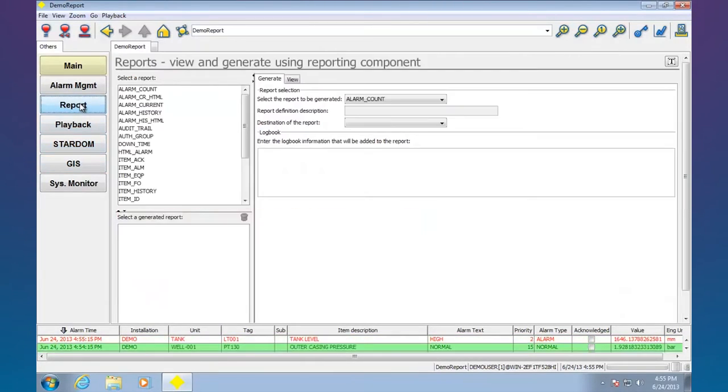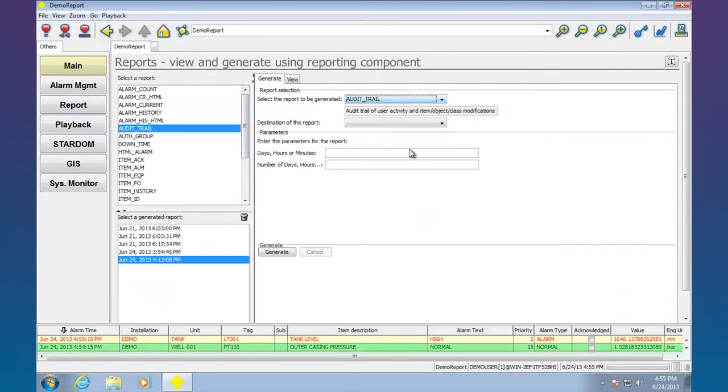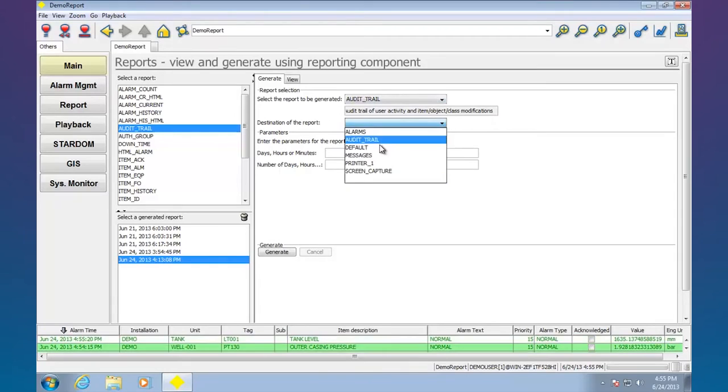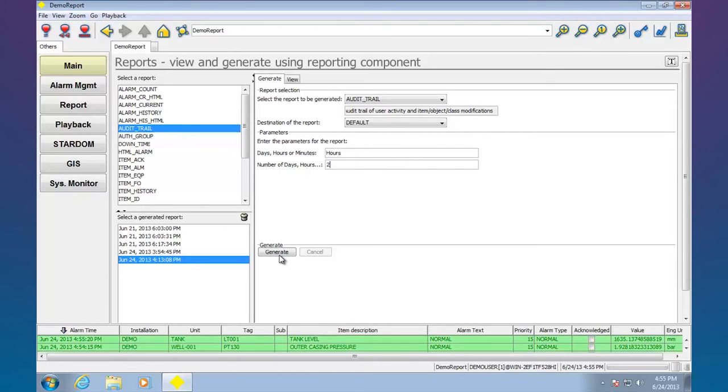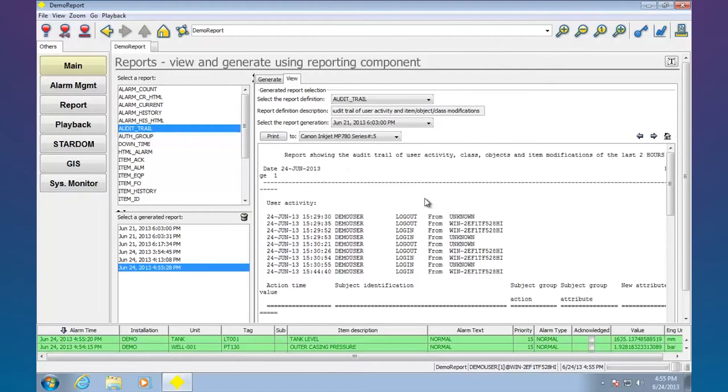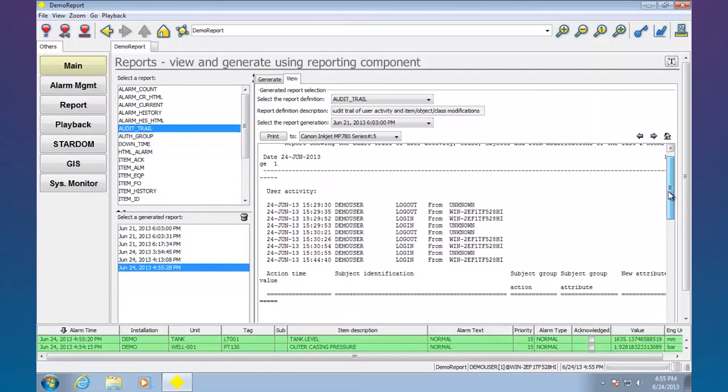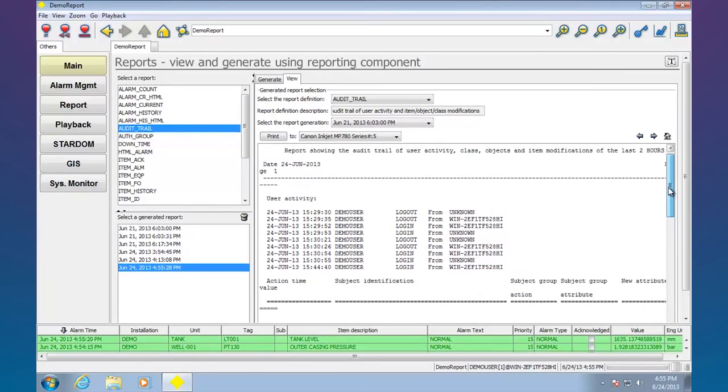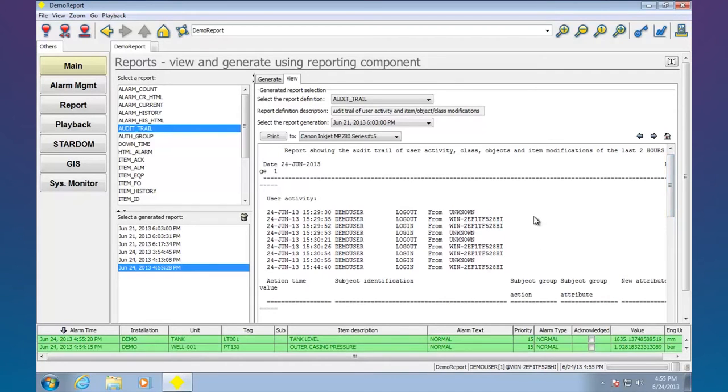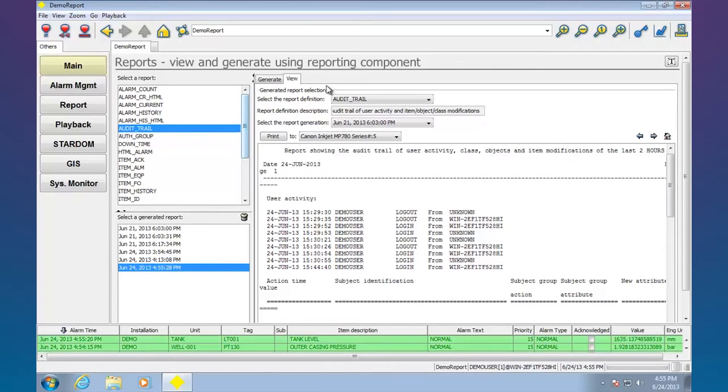I've got a full reporting system as well. I can do something like audit trail here. I can say I want to go hours, the last two hours. Generate a report. There it is. Those are all the people that logged in and logged out. I wasn't editing the system. If I had gone ahead and edited the system, all the edits and changes are there. So if you're in the pharmaceutical area, we've got full support for 21 CFR part 11 audit trail type requirements.